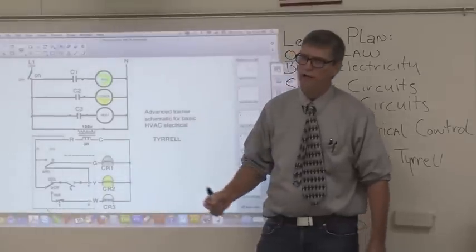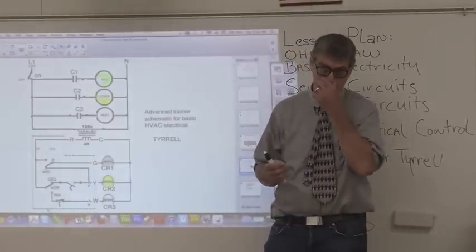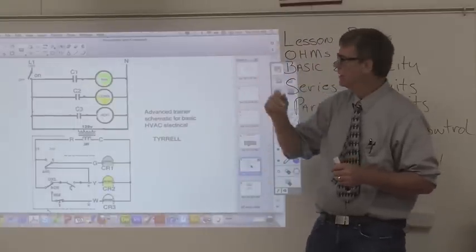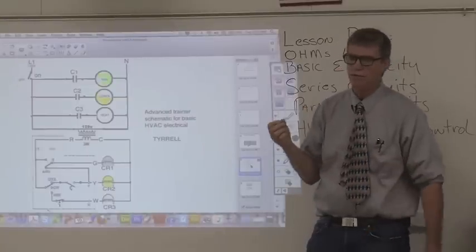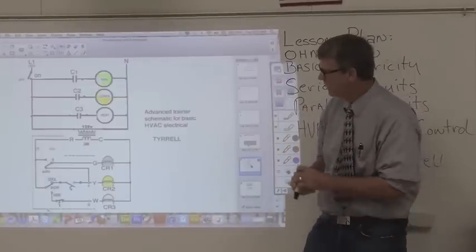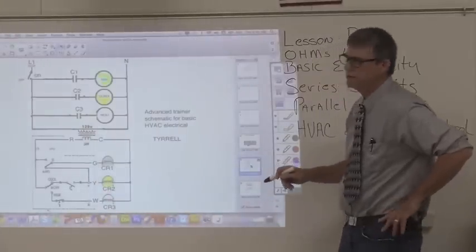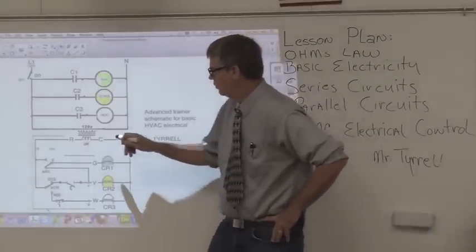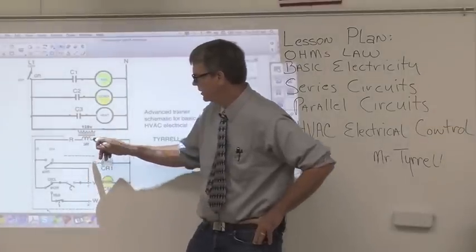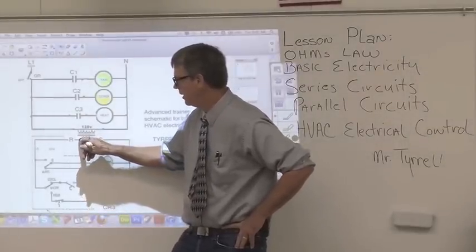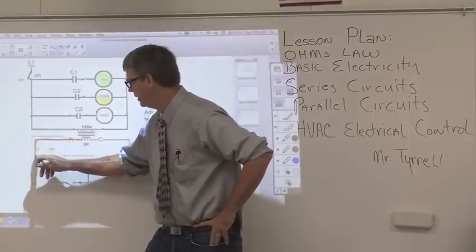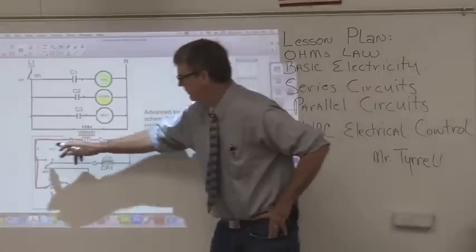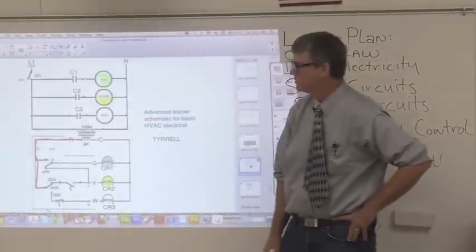The reason we do that mainly is for safety, but it's also a cheap way to run your wires to all the different components. You can run that wire inside the walls and not worry about putting it in conduit because 24 volts is a safe voltage. When we step that down to 24 volts, if this is the secondary side of the transformer and this is our hot side, we call that R.